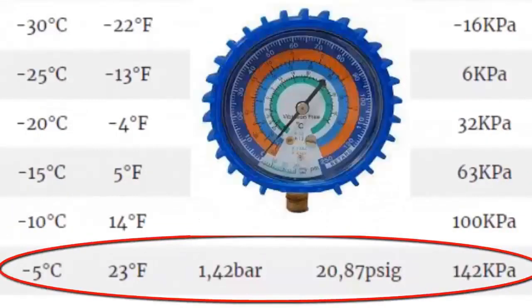3. To achieve a temperature of minus 5 degrees Celsius in the evaporator, equivalent to 23 degrees Fahrenheit, a low gauge pressure of 1.42 bars is needed, equivalent to 20.87 PSIG or 142 kilopascals.